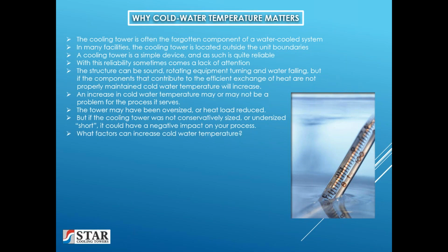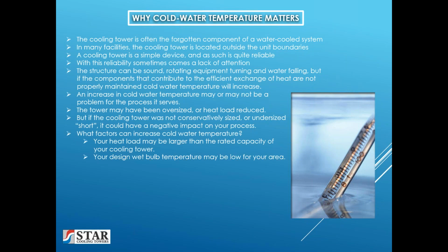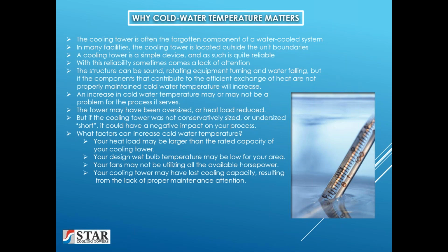So what factors can increase cold water temperature? Your heat load may be larger than the rated capacity of your cooling tower. Your design wet bulb temperature may be low for your area. Your fans may not be utilizing all the available horsepower. And finally, your cooling tower may have lost cooling capacity resulting from the lack of proper maintenance attention.